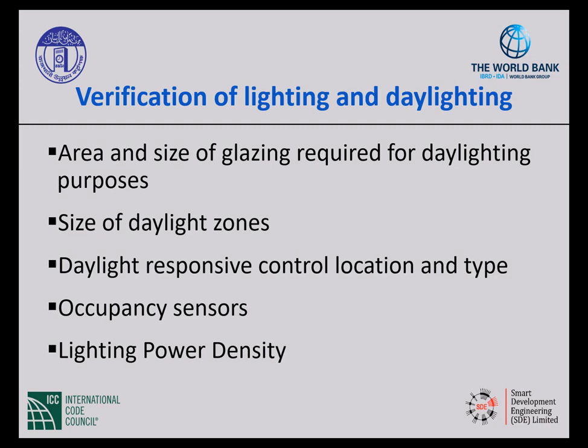It's really up to the designer to specify on the set of plans, here's my daylight zone. Yep, I've accounted for it. And oh, that daylight responsive control that's supposed to be halfway in the middle, there it is. And this is the location. That really should be called out on the plans, so that all we have to do is verify it.